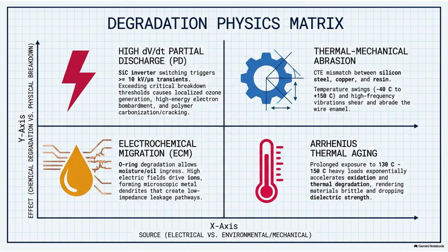Because when you look at the root cause analysis, the primary instigator is something the EV industry usually champions as, like, the holy grail of efficiency. Right, the silicon carbide inverters. Yeah, the SiC inverters. Why does our source material paint them as the villain here? Well, what's fascinating here is the sheer engineering paradox of high-performance components. Silicon carbide inverters are revolutionary because they switch voltages incredibly fast, which minimizes energy loss. Okay. But that extreme switching speed creates an electromagnetic nightmare downstream, specifically a phenomenon known as high-frequency dV/dt. Yeah, just the change in voltage over the change in time. With SiC architectures, we're looking at violent voltage rise rates, frequently exceeding 10 kilovolts per microsecond.